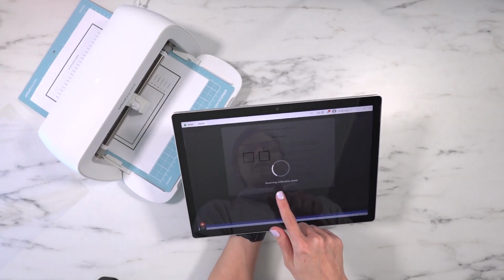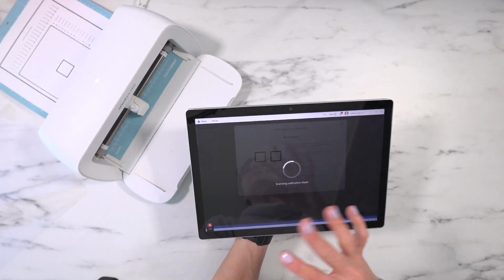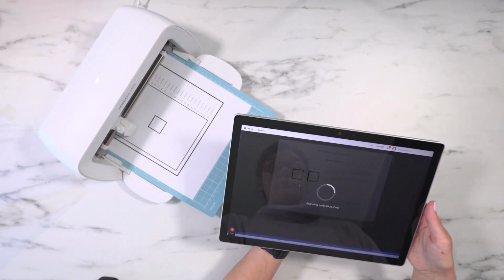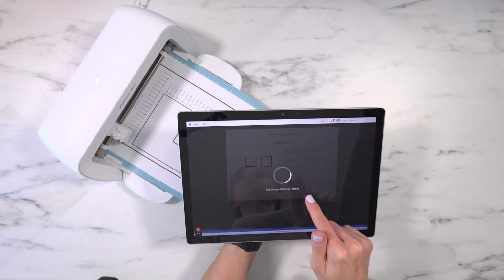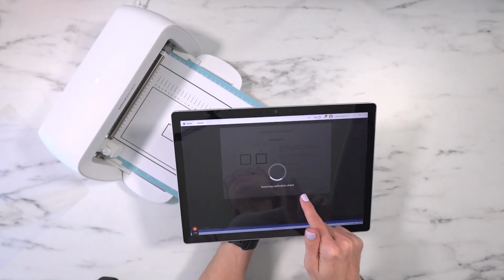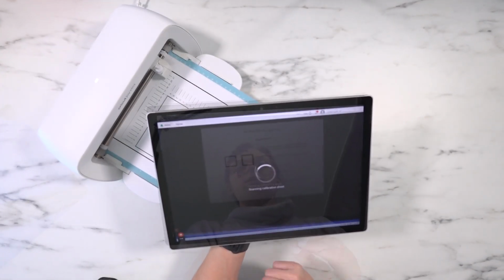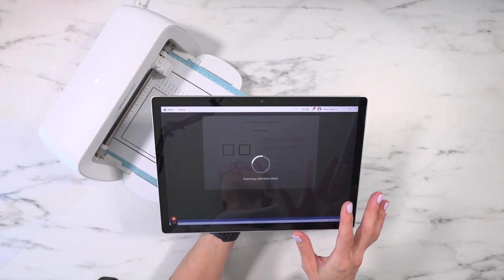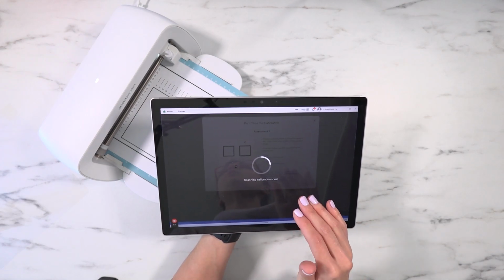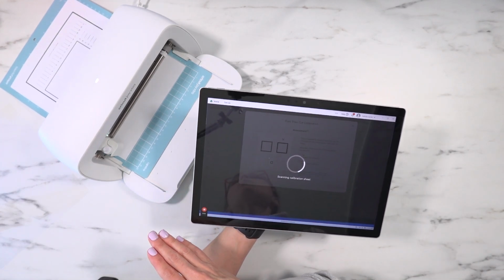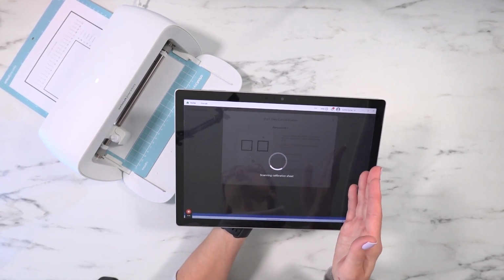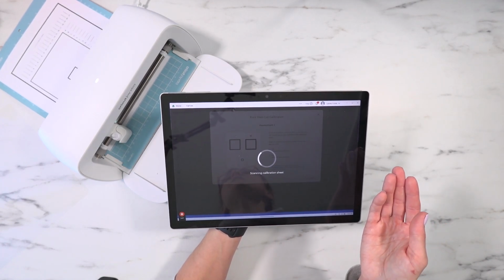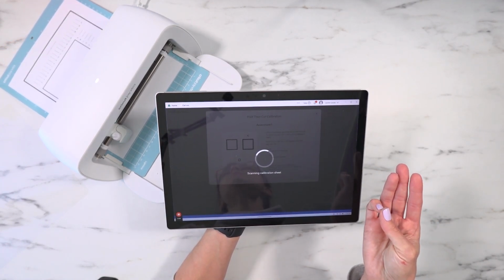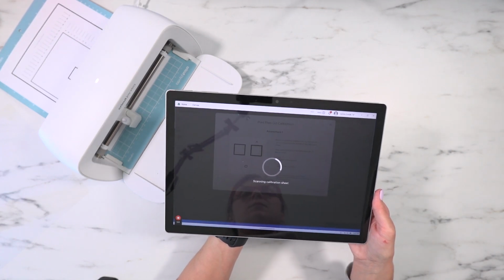And it just says it's scanning the calibration sheet. So this is what's going to take a minute. But after it's done, we're just going to follow the prompts and answer yes or no, so we can continue through the calibration process. Now, for some reason, if the cuts aren't accurate and you're answering no to questions, it will prompt you to print this out again and start over. Sometimes you have to do that. I believe it'll let you do that up to 3 times, and I have done that in the past.